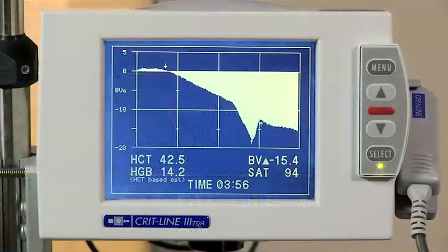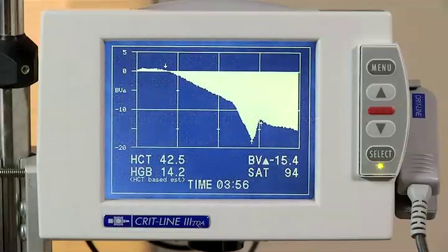During the next several minutes, you see the blood volume profile has increased significantly. This means that the patient is continuing to refill into the vascular space and has more fluid to remove. A refill check can be performed by following these steps. Set the UF rate to minimum. Record the hematocrit value as displayed by the CritLine monitor. Wait 10 minutes and record the hematocrit as displayed by the CritLine monitor. If the hematocrit has decreased by 0.5 during the 10 minutes, then the patient is considered to have vascular refill.